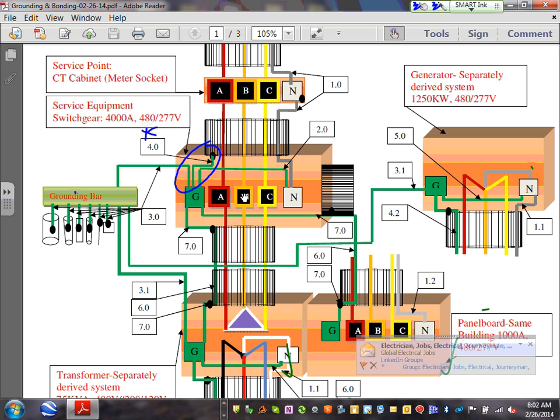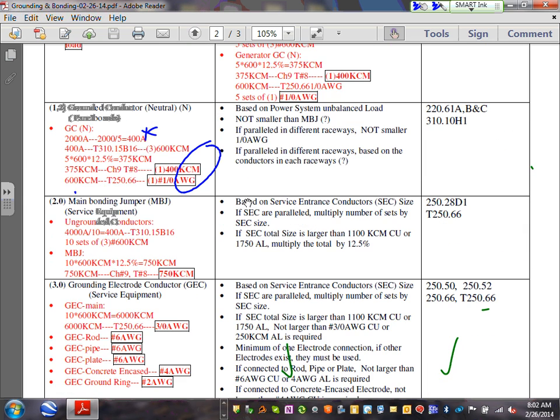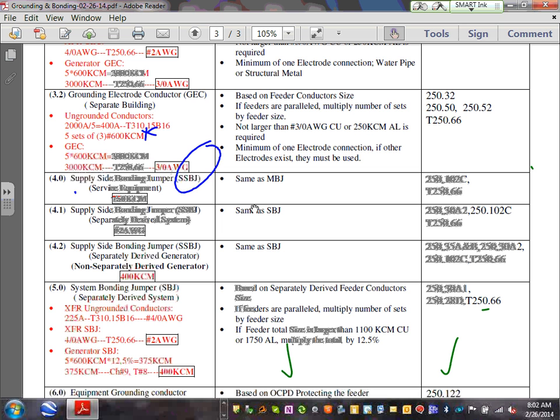Supply side bonding jumper, it takes the metallic conduits, Adam, that are coming from the bottom of the switchgear and ties them to the ground bar inside the switchgear. It's called supply side bonding jumper. Now remember, we are at the service. Supply side bonding jumper at the service. So if you guys go all the way to 4, here's 4. Can you guys see what 4 is? 4 is called supply side bonding jumper.